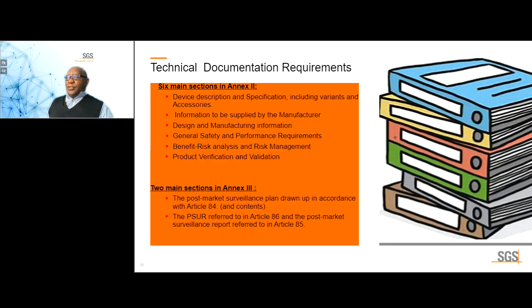So, Annex 2, technical documentation requirements. This will be what I call traditional technical documentation. This is information pre-market, and there are 6 main sections: device description and specification, which includes variants and accessories; information to be supplied by the manufacturer, which is essentially GSPR 23, which would cover the labels and IFU; design and manufacturing information. This is where you must disclose every bit of information relating to manufacturing of your device, the design and manufacturing of your device, including the adjuvants, your processing aids, everything.